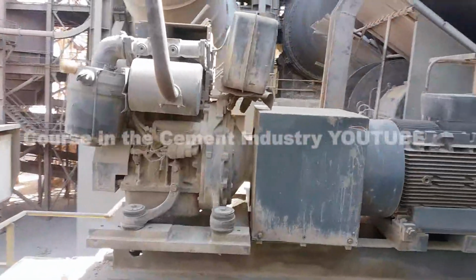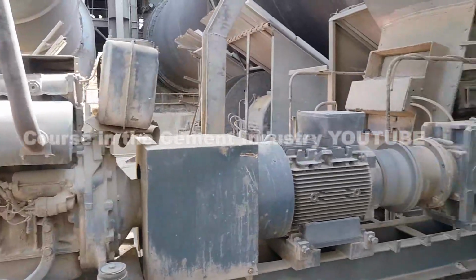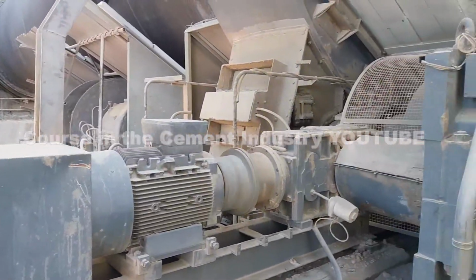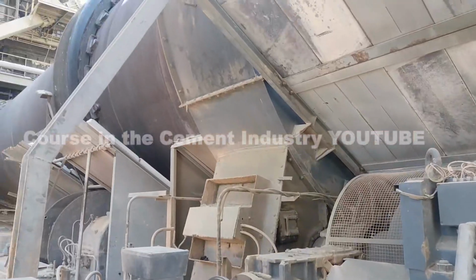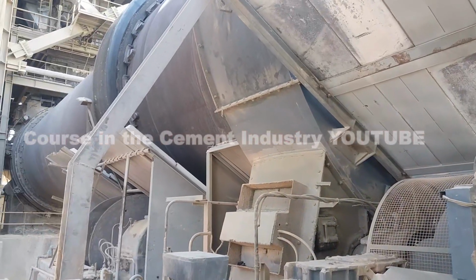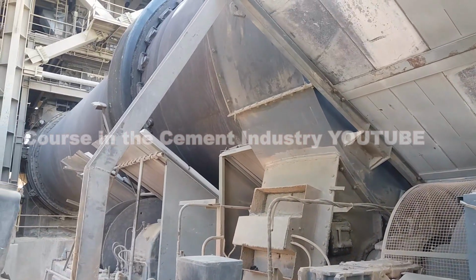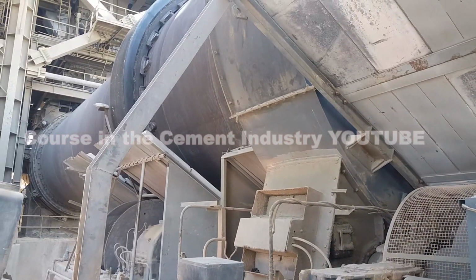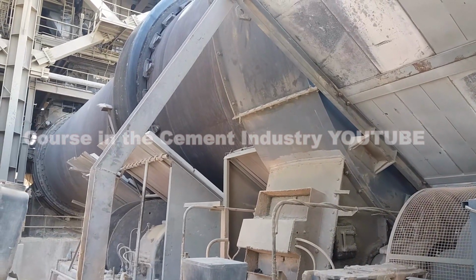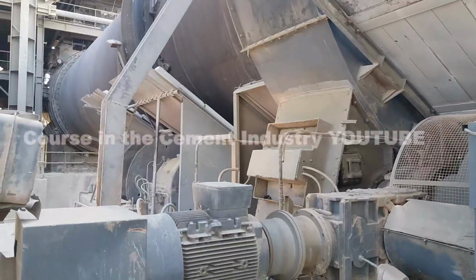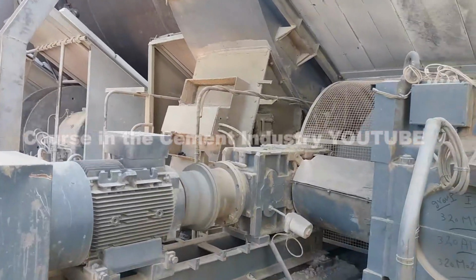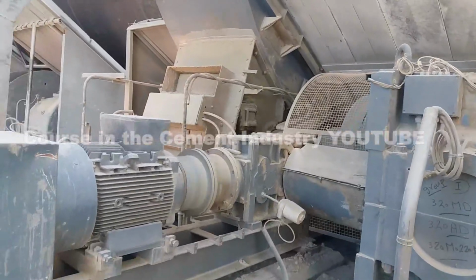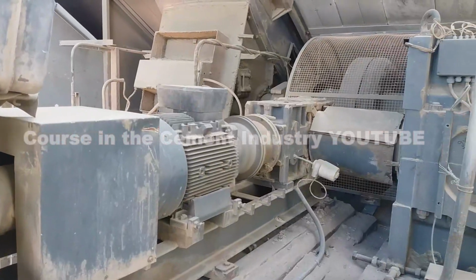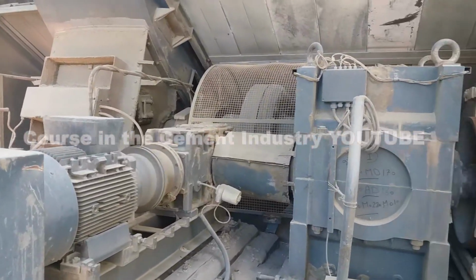5. Auxiliary drive, emergency or inching drive. Components: a smaller motor, often diesel or a separate electric motor, and a dedicated small gearbox. Function: used during power outages or maintenance. It turns the rotary kiln very slowly to prevent bending, or sagging, of the shell while it is hot.